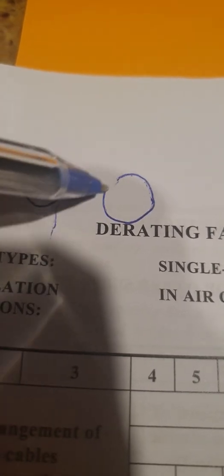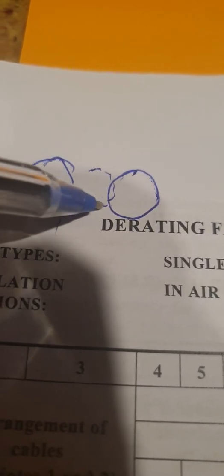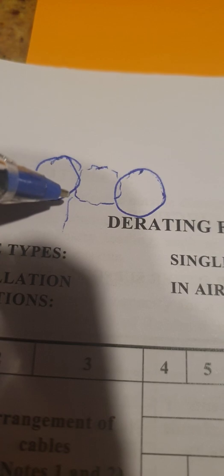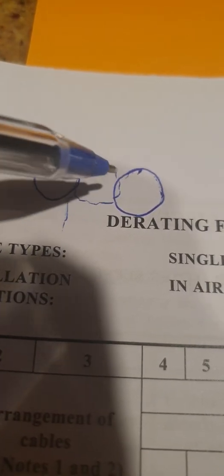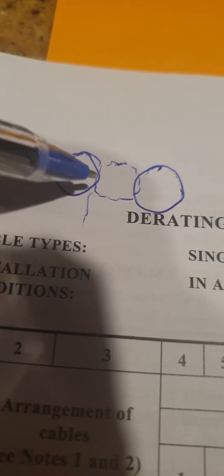What they're saying is that if I have three cables spaced in a bar, I need to have a minimum of one cable clearance distance between the two cables for the de-rating to work. If I have the largest cable, that has to be the minimum size diameter for the de-rating to work.